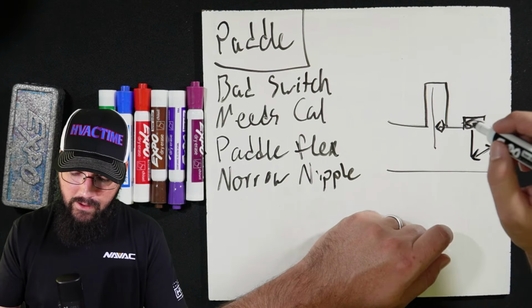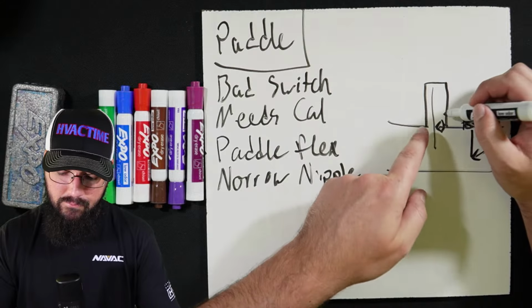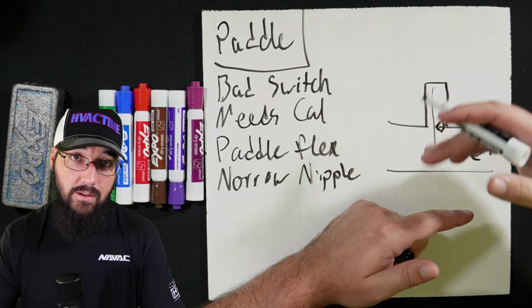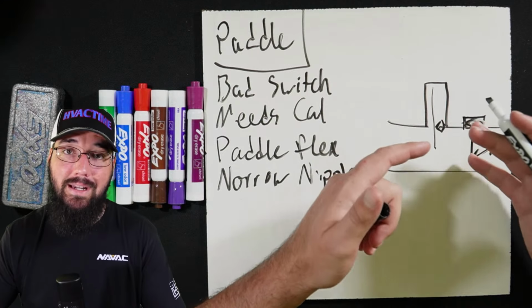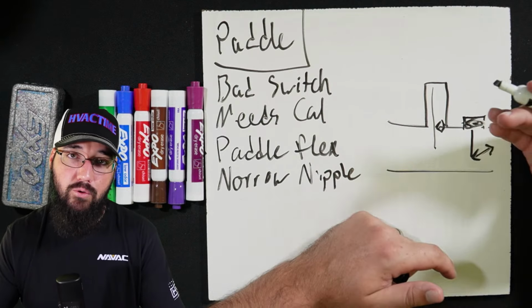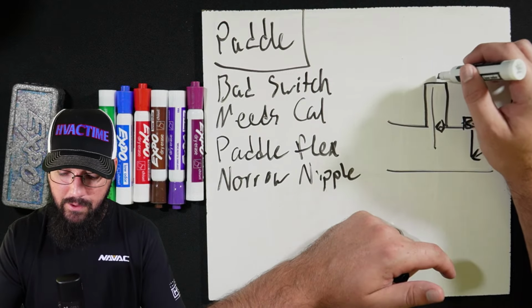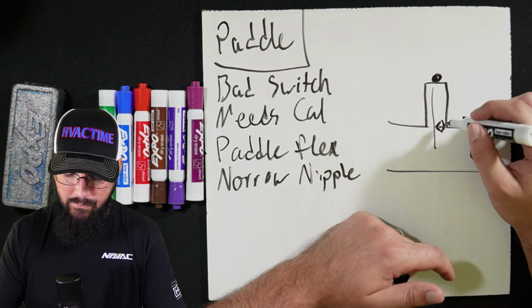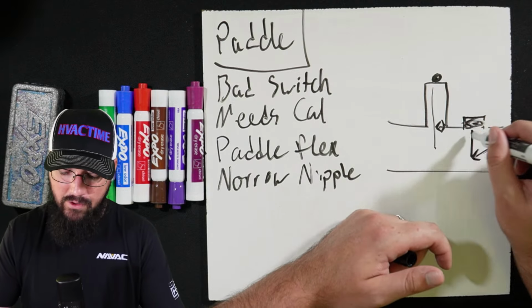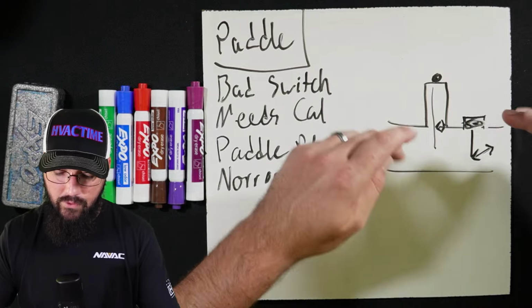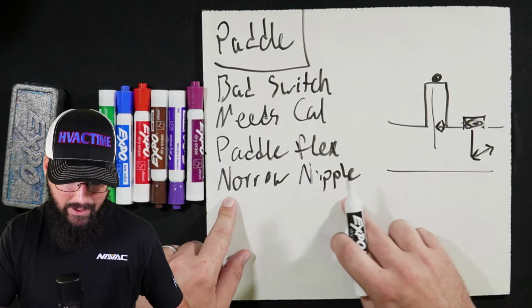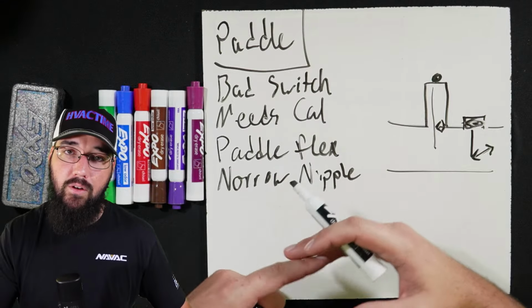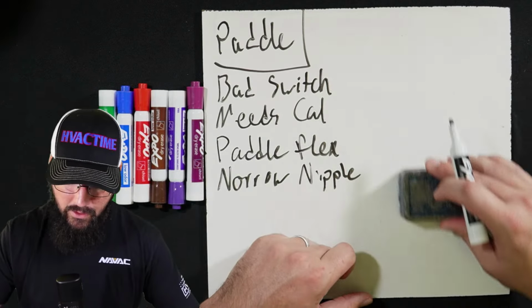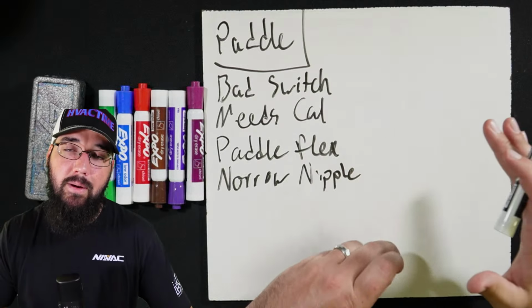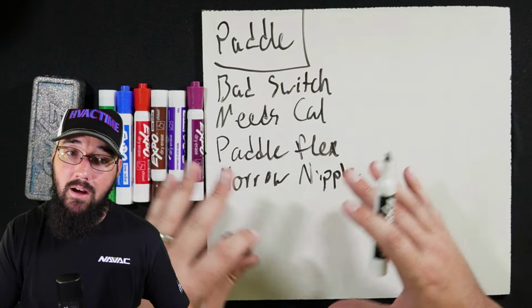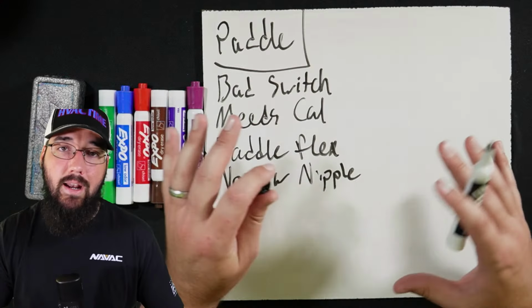If you are going to need to put it on a nipple to extend the distance for whatever reason, it needs to be a 1 inch size at least. And you could always put a reducer down from 3/4 to 1 inch up here at the threadolet. But that 1 inch is needed in order to have enough swing in the paddle. If you don't have that, the threadolet itself or the nipple extension, whatever the case may be, very well could be preventing that paddle from actually making the switch. It might do it sometimes and it might not. That may be where it's being erratic.